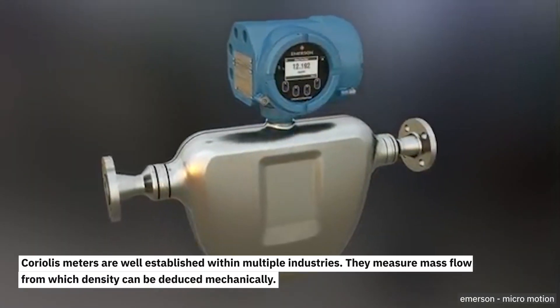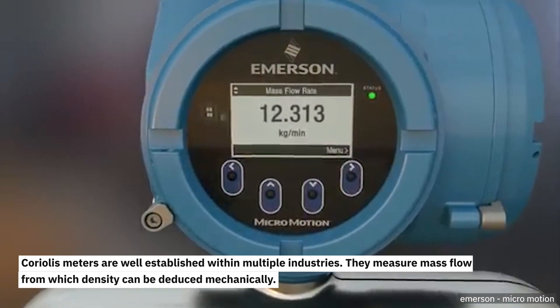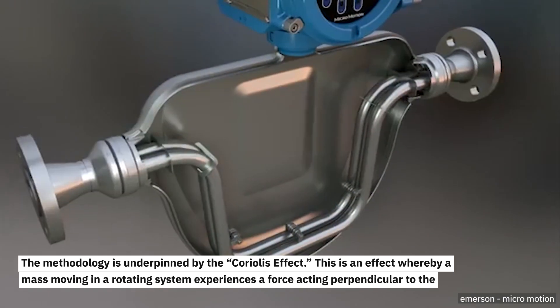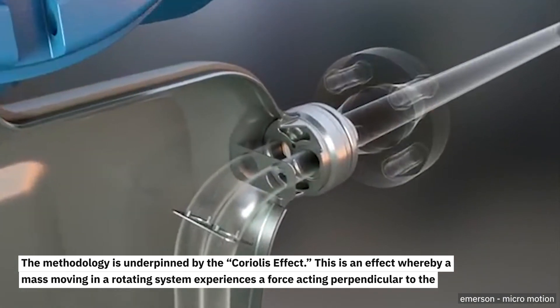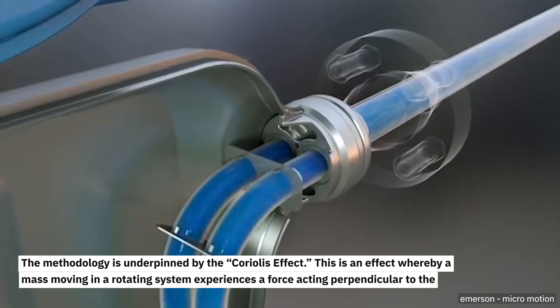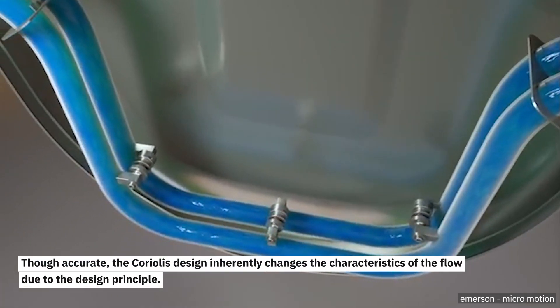Coriolis meters are well established within multiple industries. They measure mass flow, from which density can be deduced mechanically. The methodology is underpinned by the Coriolis effect. This is an effect whereby a mass moving in a rotating system experiences a force acting perpendicular to the direction of motion and to the axis of rotation. Though accurate, the Coriolis design inherently changes the characteristics of the flow due to the design principle.